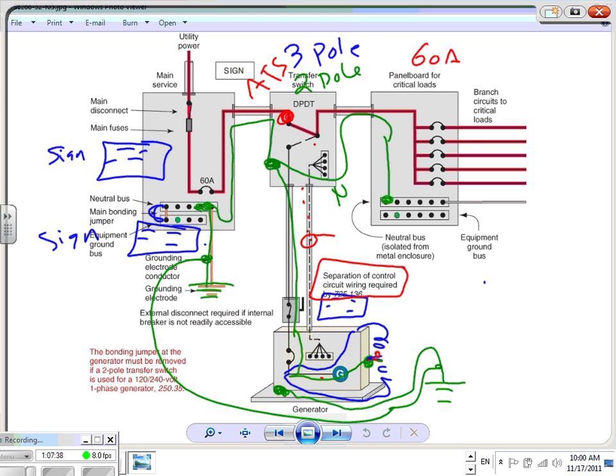And we will talk more about this, guys, as we move into the commercial industrial building. That's how we do it, an auto transfer switch. If this is an emergency load in a hospital or anywhere in the building, this must be an auto transfer switch. No option. Manual transfer switches are not an option for a legally required system or an emergency system. A standby system like this, it's an option. Any question, guys, about this?